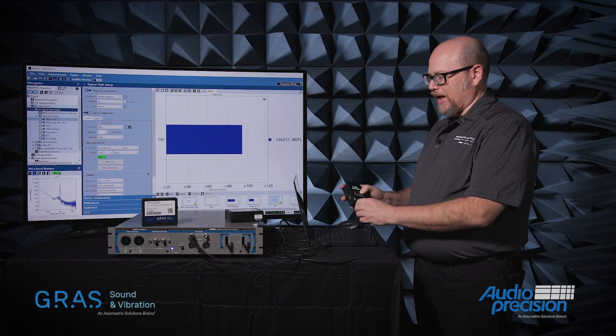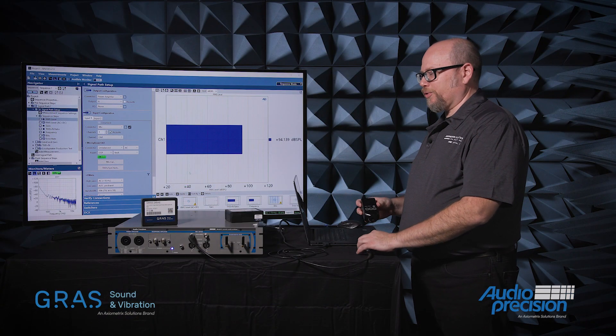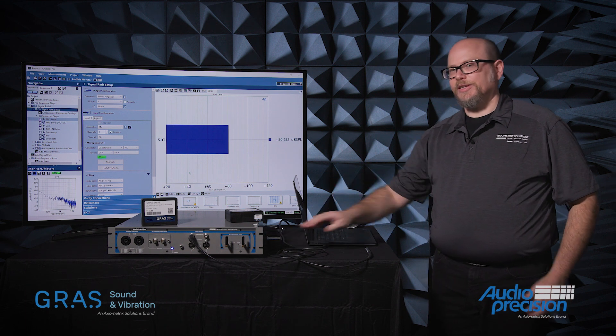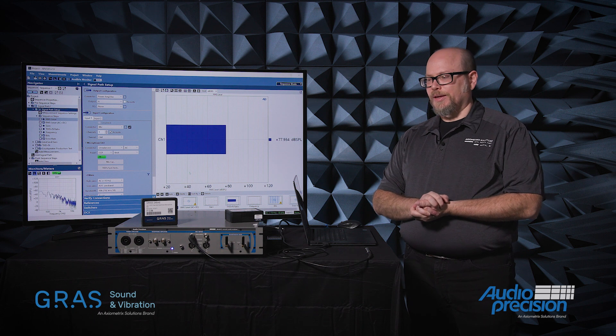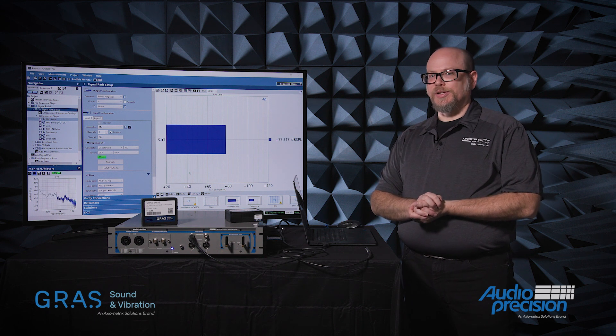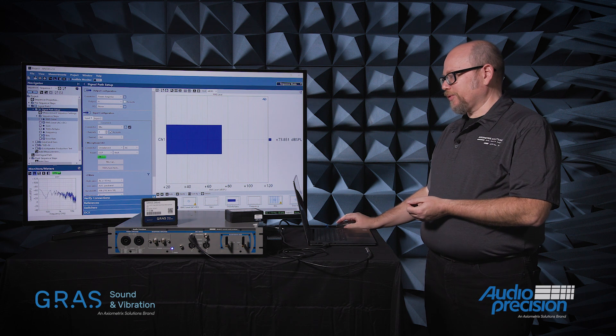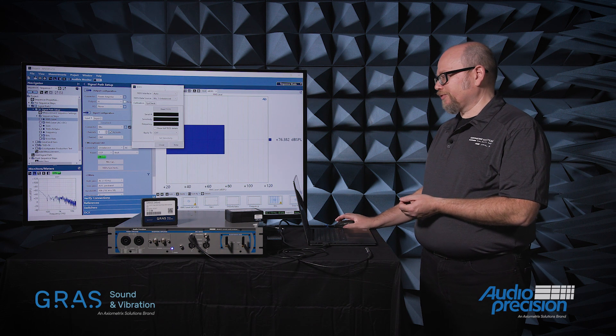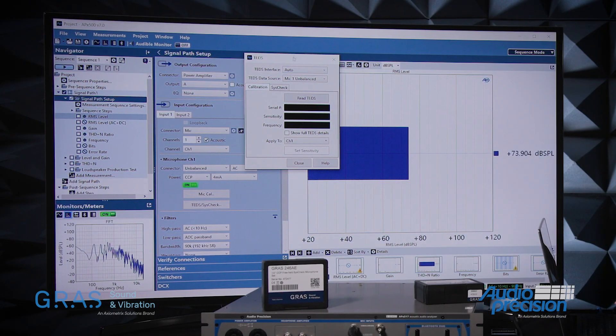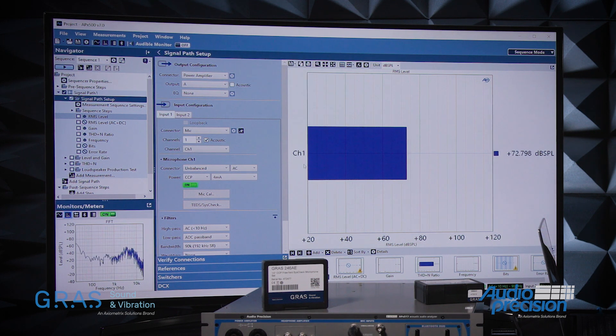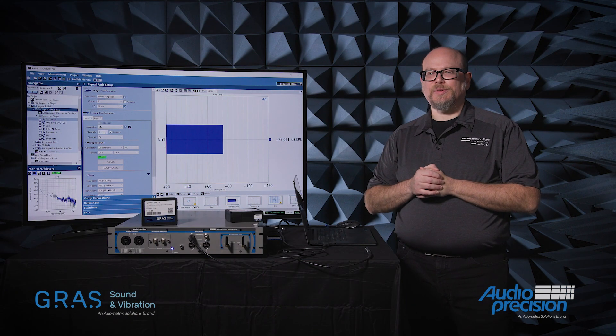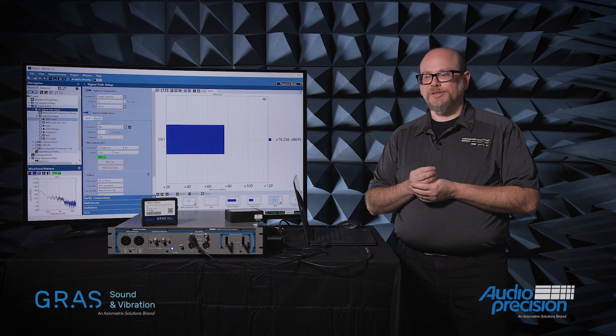That is certainly a classic and pretty reliable way to do it, but it does have the problem that I need to have physical access to the microphone. Now I can do this touch-free. In our system, we can also grab the calibration information via TEDS. I open the TEDS control panel in the APX500 software, I read the TEDS data, and I set the sensitivity, and I've achieved the same thing — I've captured the sensitivity of the microphone into our measurement setup.